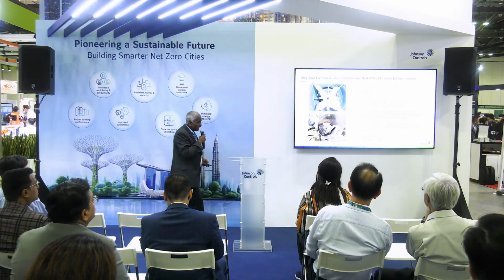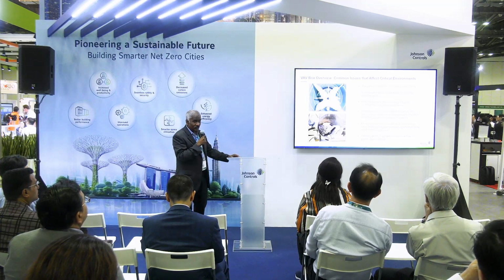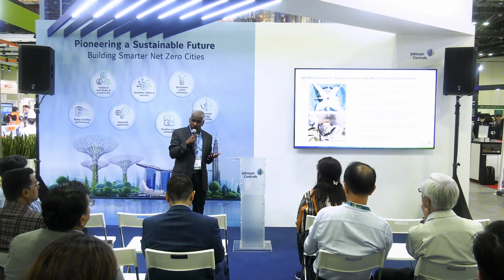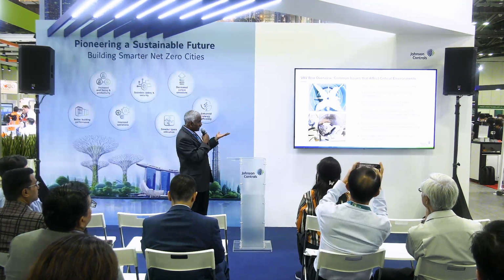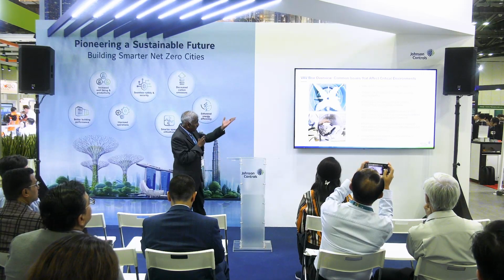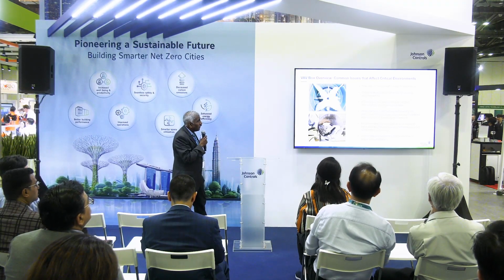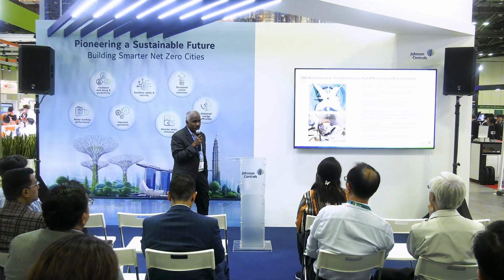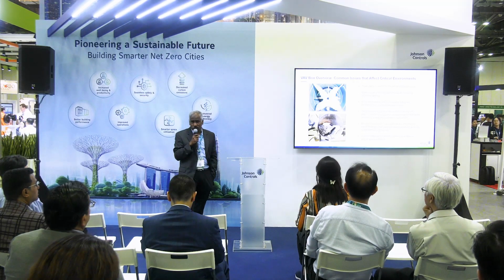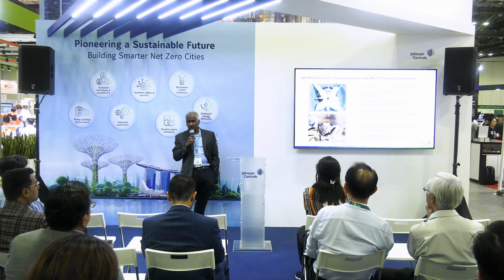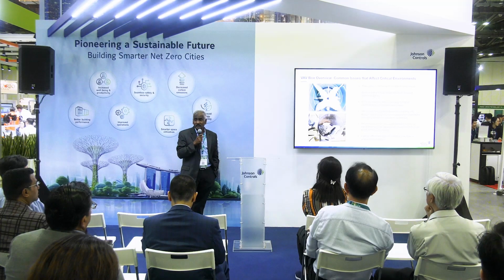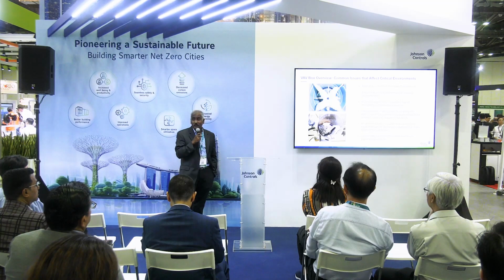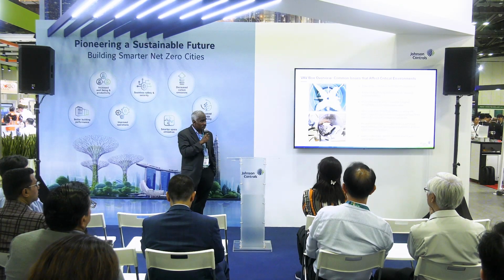So what are the issues with the VAV box? Some customers ask for VAV boxes, but we don't recommend them. These are some of the challenges. The first one is the time delay problem for critical spaces. If someone is opening the door, closing the door, or a nurse is coming in, or someone is bringing in supplies, you still need to maintain the positive pressure. Or for an isolation room, you need to keep a negative pressure. You don't want the germs to go out. So this is very, very important.